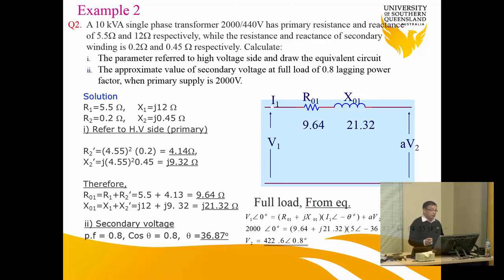Another example useful for design: referring to the primary side, we calculate resistances and reactances, then get the primary side values, and using the power factor, calculate the secondary voltage. Under full load condition, we get V1 and V2 using these formulas.